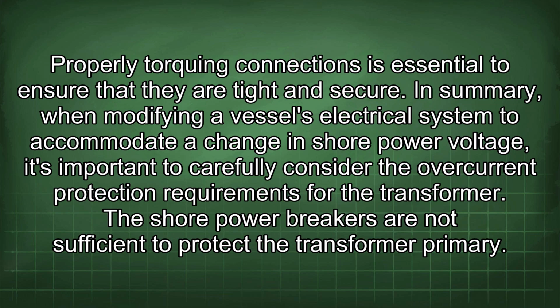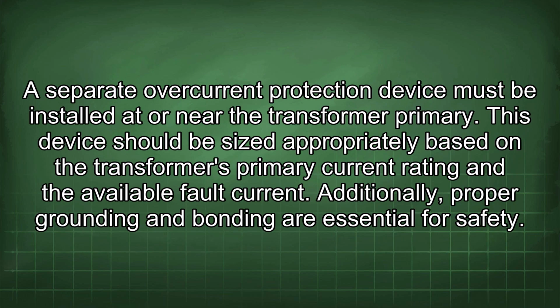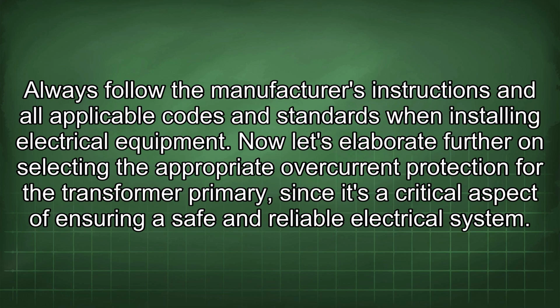In summary, when modifying a vessel's electrical system to accommodate a change in shore power voltage, it's important to carefully consider the overcurrent protection requirements for the transformer. The shore power breakers are not sufficient to protect the transformer primary. A separate overcurrent protection device must be installed at or near the transformer primary. This device should be sized appropriately based on the transformer's primary current rating and the available fault current. Additionally, proper grounding and bonding are essential for safety. Always follow the manufacturer's instructions and all applicable codes and standards when installing electrical equipment.